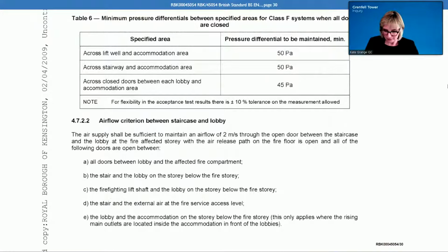One of the things to think about is that when an extract system is extracting smoke, what we're worried about is smoke leaking from one floor to another up the shaft. So if we're extracting smoke and you have a damper on the floor above, you're extracting past the damper. Therefore the smoke's unlikely to leak back in. I don't know if that's a good diagram, but it's unlikely to leak back in because you're extracting. I think that was the principle on which the 2012 version of the guide was based. But we get advancements in the industry about quality and standards. So when smoke dampers are available which have a degree of leakage, but still leak smoke, then why not use them? And I think that's resulted in their inclusion in the 2015 version.